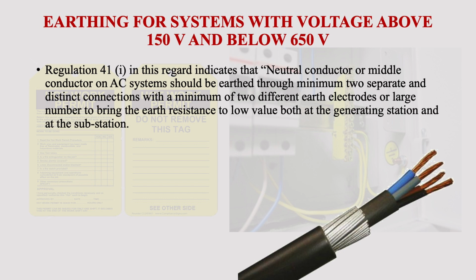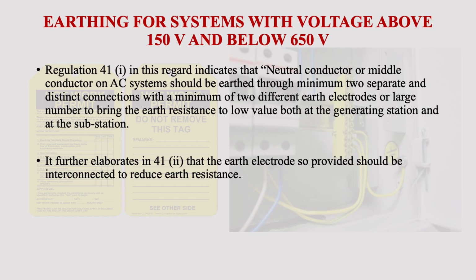Regulation 41(1) in this regard says the neutral conductor of a 3-phase 4-wire system and the middle conductor of a 2-phase 3-wire system shall be earthed by not less than 2 separate and distinct connections with a minimum of 2 different earth electrodes, or such large numbers as may be necessary to bring the earth resistance to a satisfactory low value, both at the generating station and at the substations. It further elaborates in 41(2) that the earth electrodes so provided should be interconnected to reduce the earth resistance.